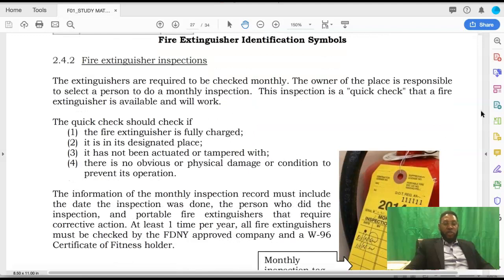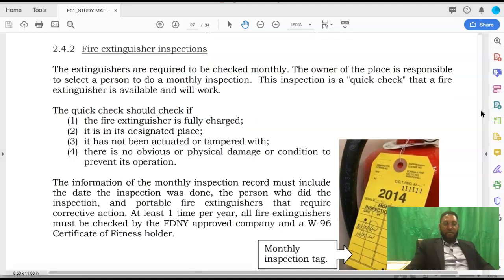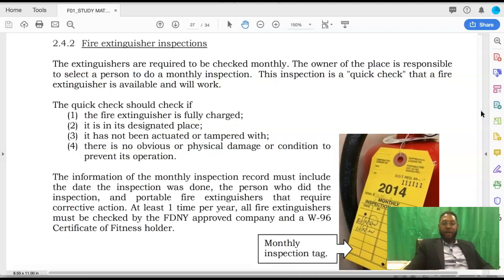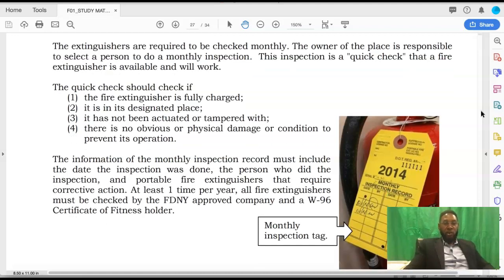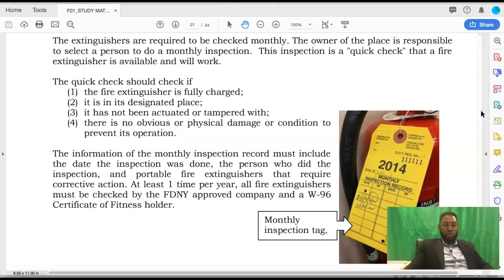So the fire extinguisher inspection. All right, every fire extinguisher must be inspected, mostly every 3 months. The extinguishers are required to be checked monthly according to the material, but most of the time it's inspected every 3 months. The owner of a place is responsible to select a person to do a monthly inspection. It might be a fire guard or the building coordinator. This inspection is a quick check that a fire extinguisher is available and will work when used.